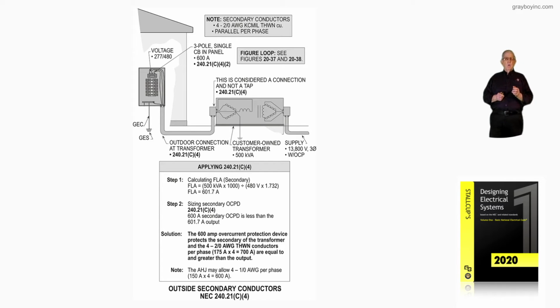So in the panel board, you can see that we just have 1 conductor per phase, but the note says no, there's 4 of them, and we just used 1 per phase to make it not as busy looking to you. But we do have 4 2-aughts parallel per phase, and we have a 600 amp 3-pole main that they're terminating to.